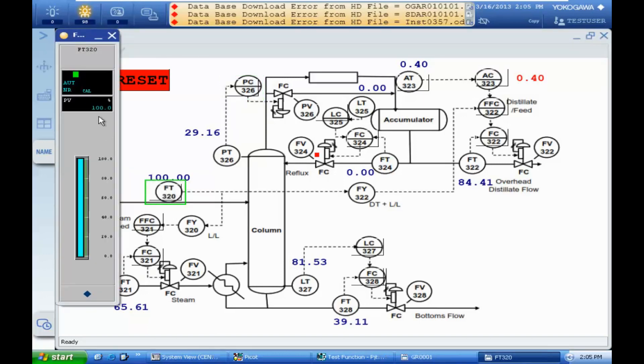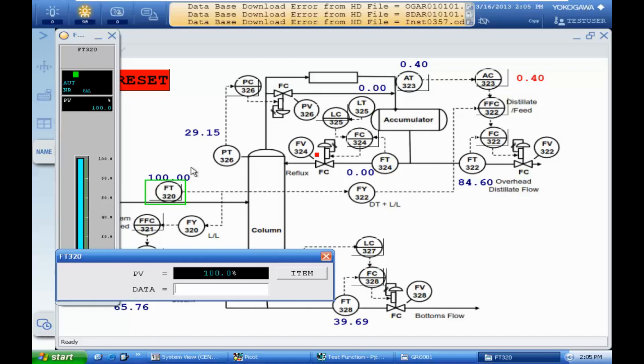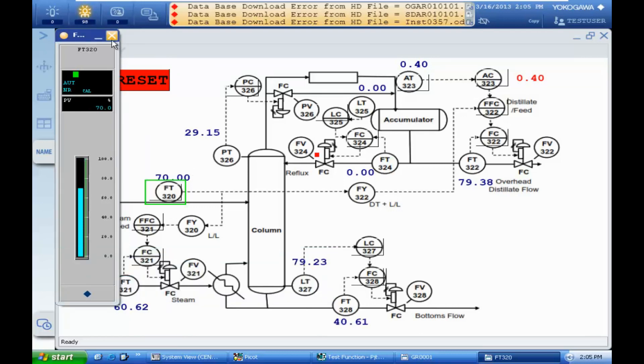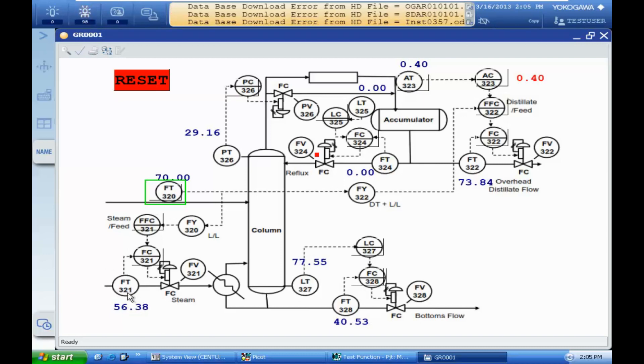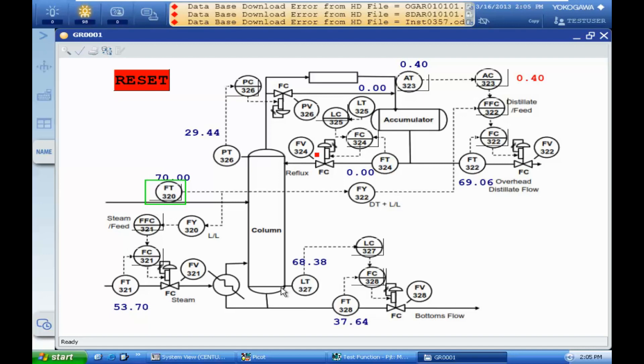I changed the flow rate back to the previous value, and again you can see that the steam flow is decreasing. The output flow is decreasing, and at the same time the level in the bottom of the column is decreasing. We will start another test.